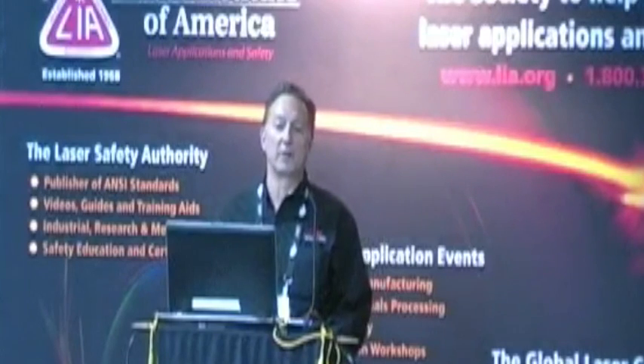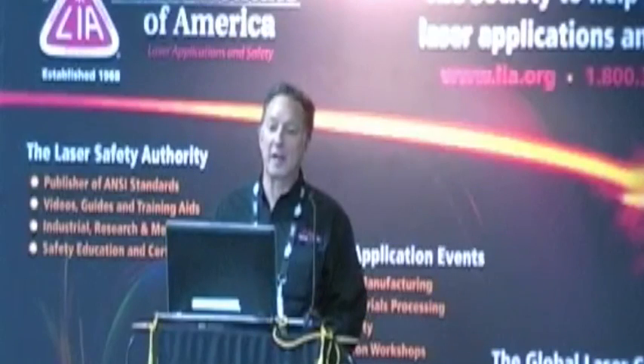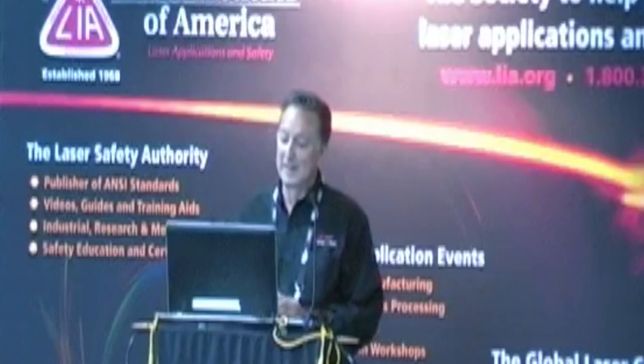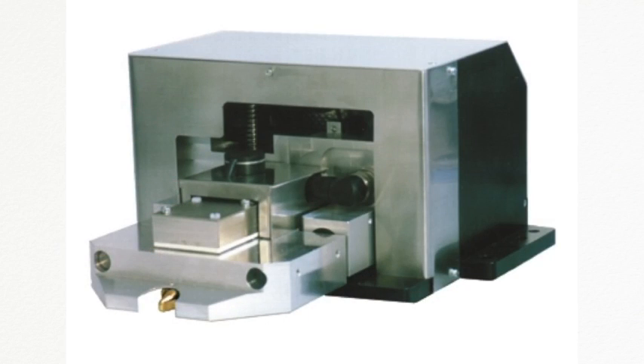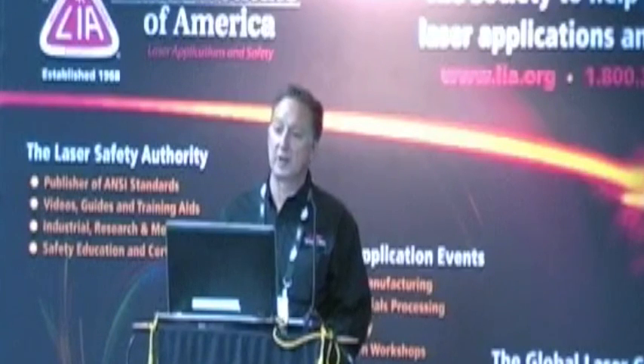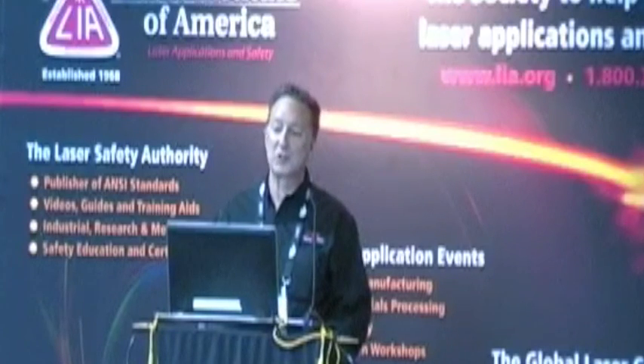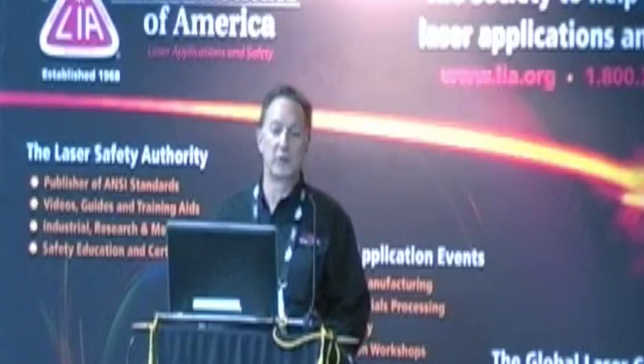Typically, measuring the profile of a laser beam is done by taking a sensor and sticking it into the beam itself, thereby capturing some part of that laser output and turning that into a measurement of its characteristics. Currently, the only practical solution for these high-power lasers is a device called the FocusMonitor from a company called Primes. However, this technique, using a spinning wire into the beam, is becoming more problematic as these powers get higher and higher. It cannot catch the critical start-up phases of what that spot might be doing, due to the fact that it takes several seconds to acquire and generate an image.